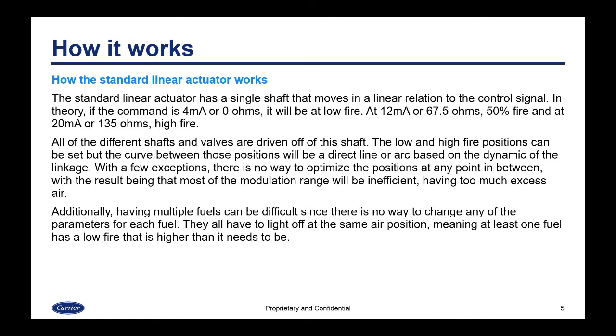The low and high fire positions can be set, but the curve between the positions will be a direct line or some kind of an arc based on the dynamics of the linkage. With a few exceptions, there is no real way to optimize the positions at any point in between, with the result being that most of the modulating range will be inefficient, having too much excess air. Additionally, having multiple fuels can be difficult since there is no way to change any of the parameters per fuel. They all have to light off at the same air position, meaning at least one of the fuels has a low fire that is going to be higher than it needs to be.